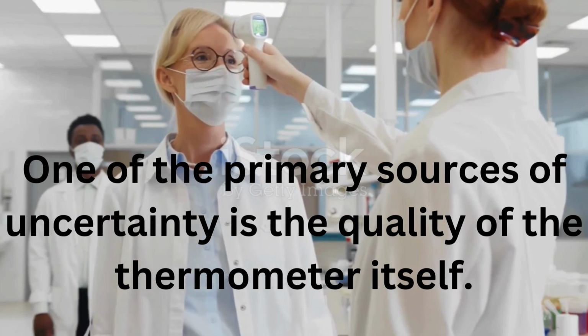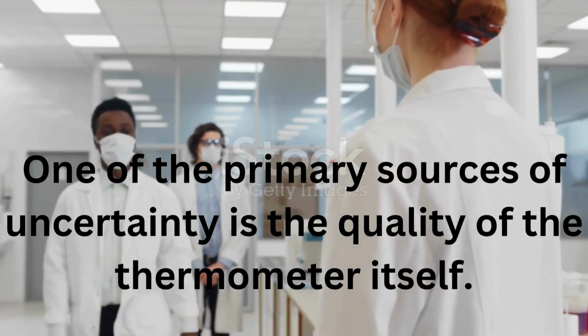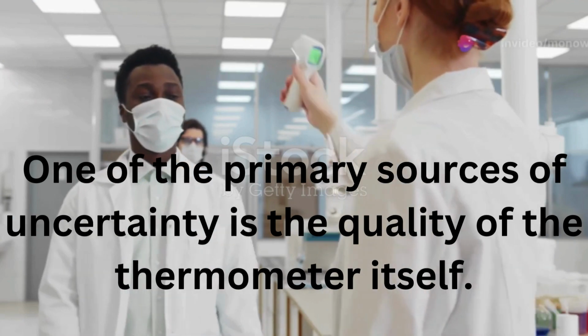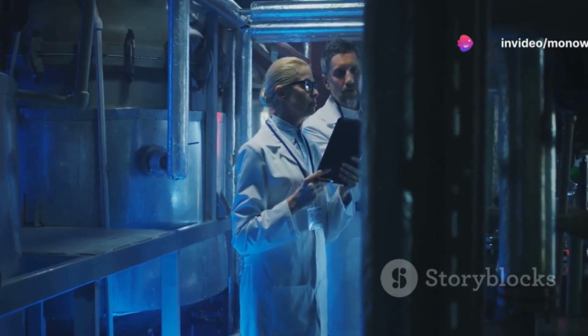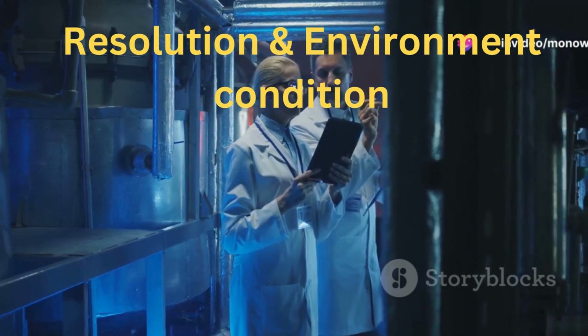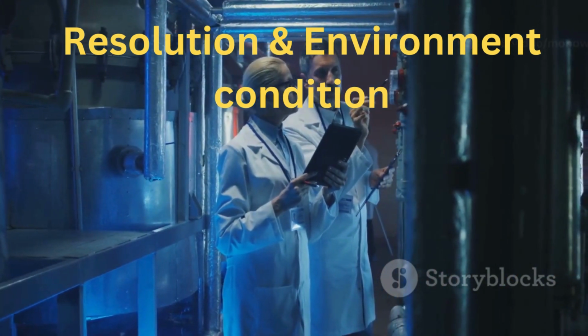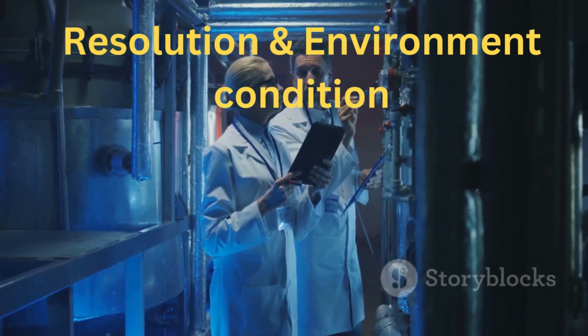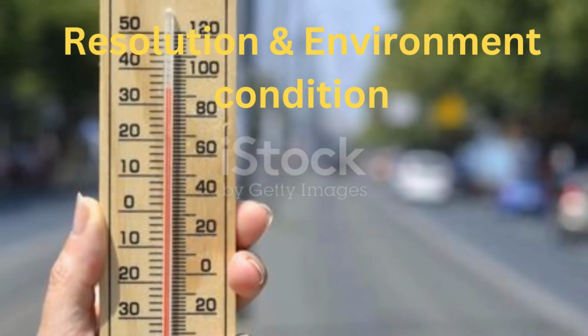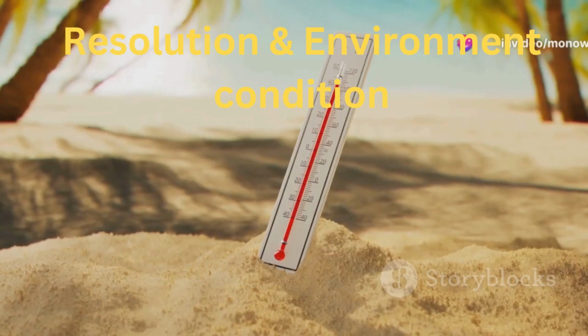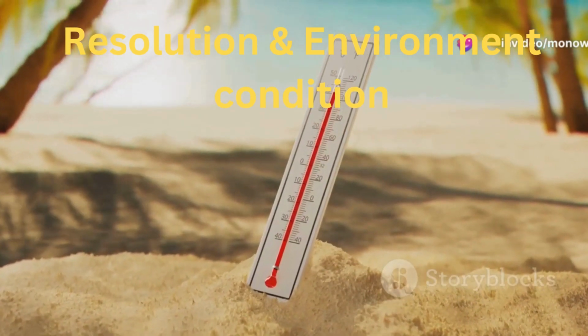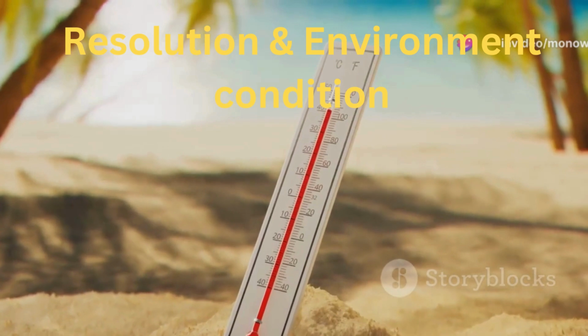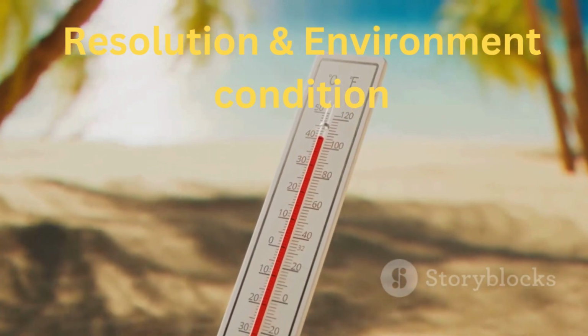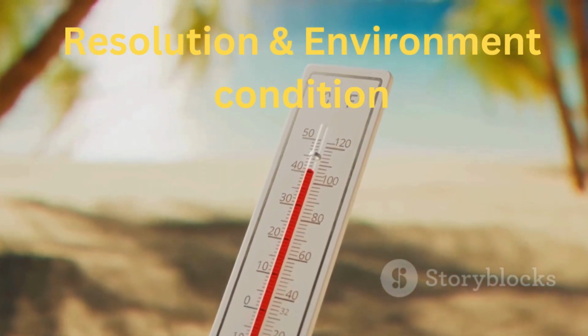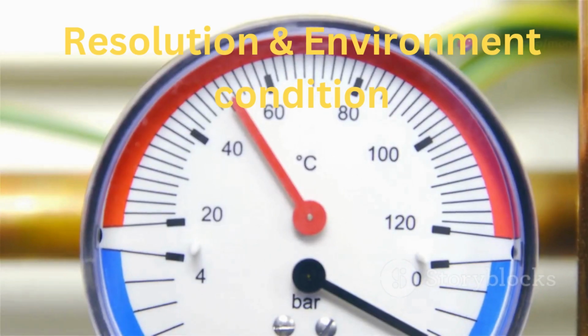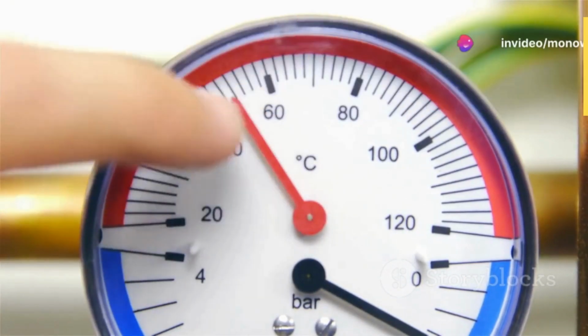One of the primary sources of uncertainty is the quality of the thermometer itself. If the thermometer is damaged or poorly made, it can lead to inaccurate readings. Furthermore, the resolution of the thermometer, meaning the smallest change it can detect, can also affect the level of uncertainty. Environmental conditions too play a significant role in thermometer calibration uncertainty. Factors such as ambient temperature, humidity, and air pressure can influence the accuracy of a calibration.